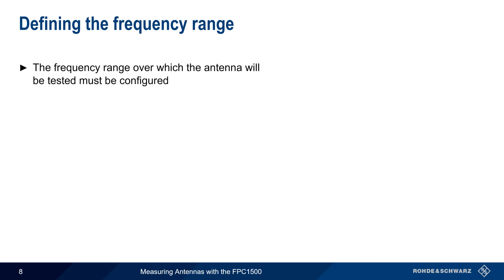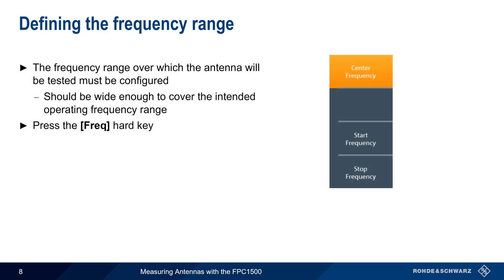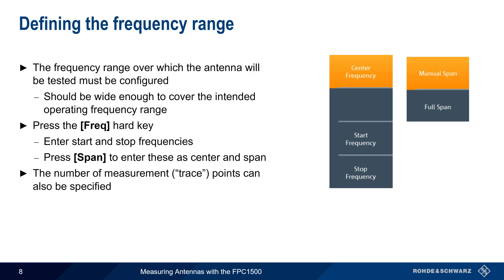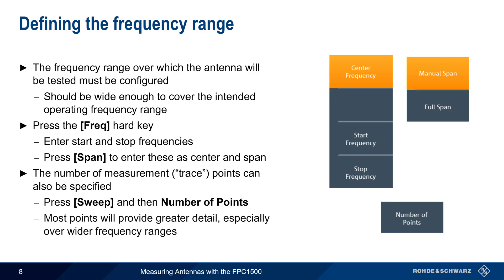We also need to define the frequency range over which the antenna will be tested. This should cover the intended operating frequencies, but may also be expanded to detect any other resonant frequencies. To define the frequency range, press the Frequency hard key and enter the start and stop frequencies. The Span key can also be used to enter these as center and span instead. The number of measurement or trace points over this span can be specified by pressing the Sweep hard key and then adjusting the number of points. A greater number of points will provide greater detail, particularly over wide frequency ranges.